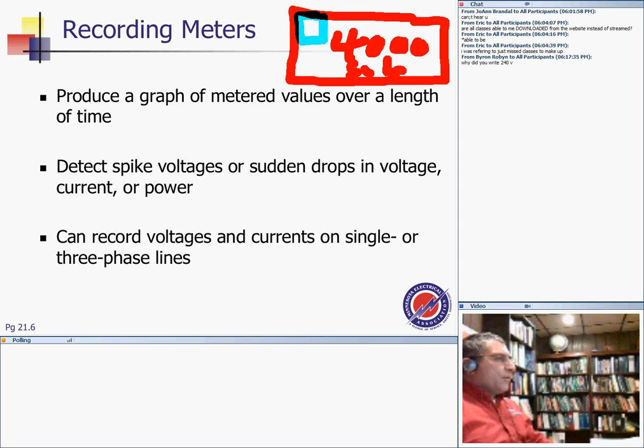So basically what we look at in the major system, these are digital multimeters. They're not just basic meters, they can give you a lot of stuff. They can give current in every phase, the voltage to ground, the voltage phase to phase of every phase, the power, the frequency, the power factor, and tell you if you have spikes in the voltage.